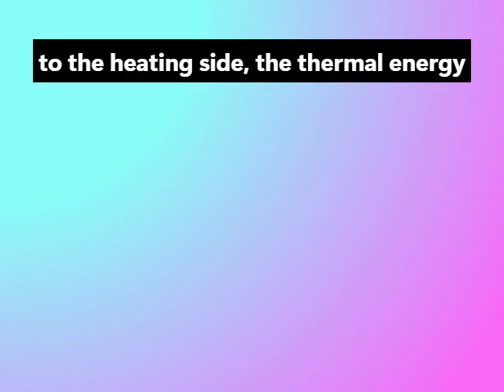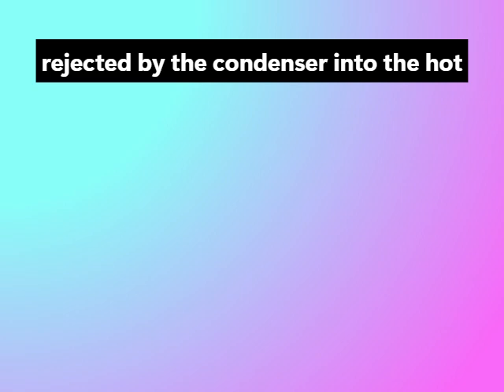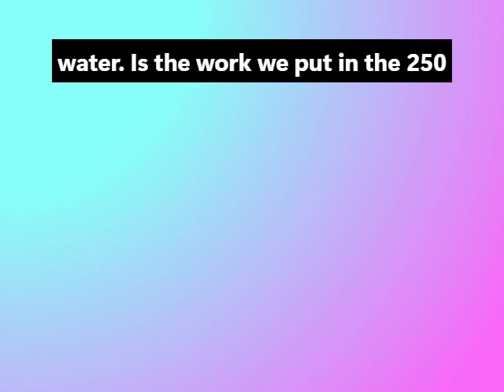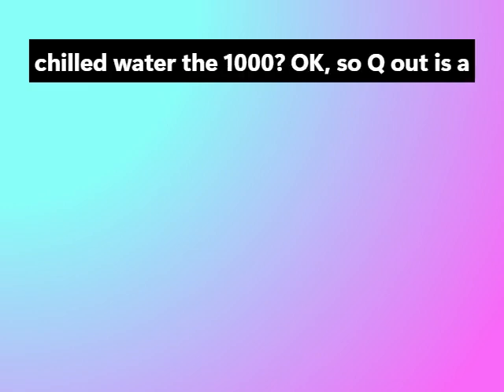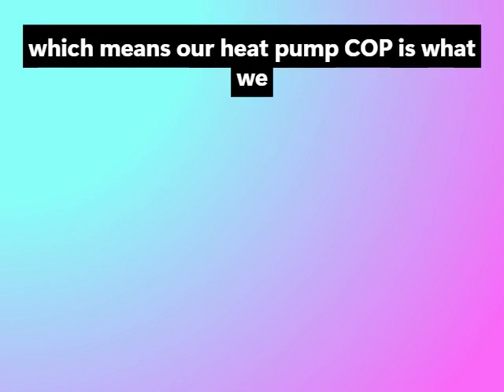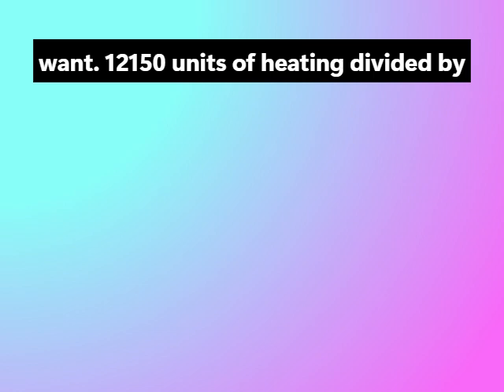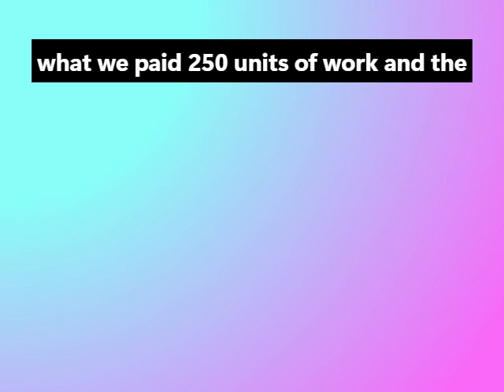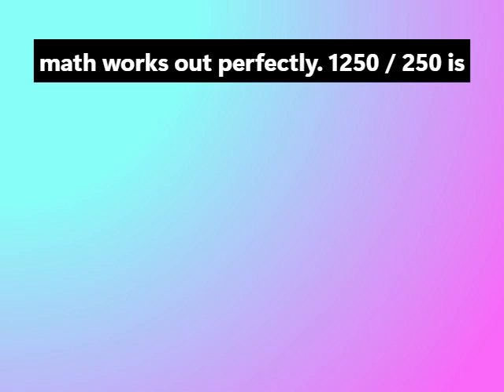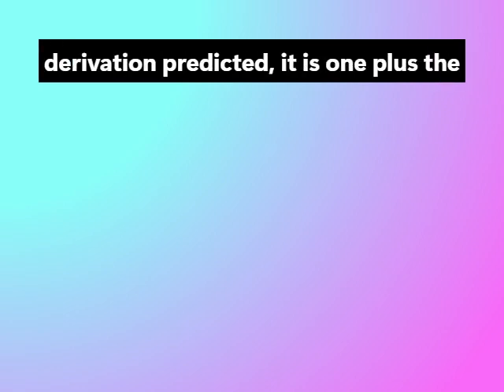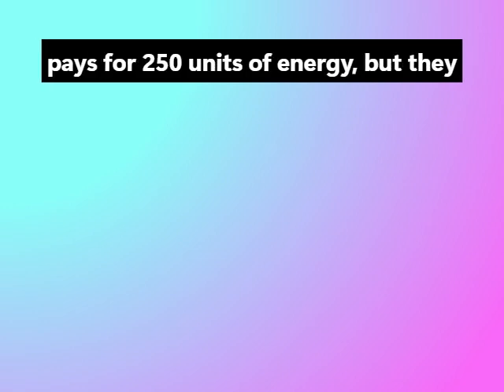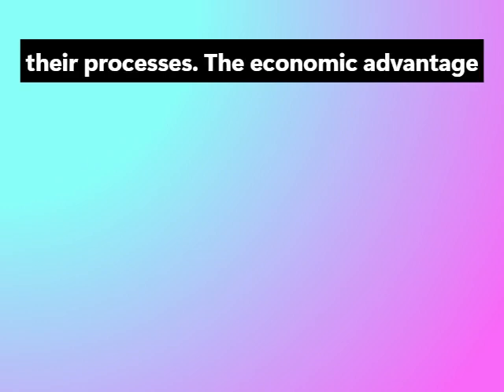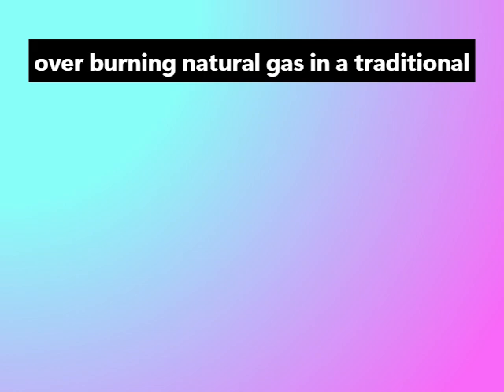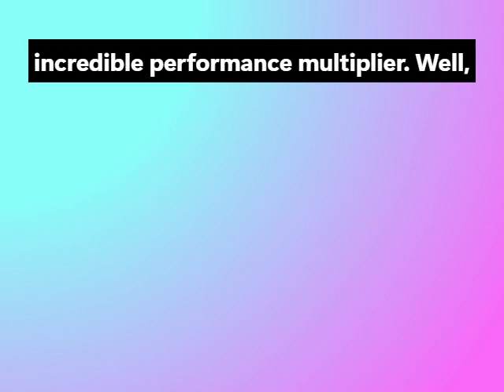Now, trace the energy to the heating side. The thermal energy rejected by the condenser into the hot water is the work we put in, the 250, plus the heat we gathered from the chilled water, the 1,000. So Q out is a total of 1,250 units of thermal energy. Which means our heat pump COP is what we want, 1,250 units of heating, divided by what we paid, 250 units of work. And the math works out perfectly. 1,250 divided by 250 is exactly 5.0. Just as the algebraic derivation predicted, it is 1 plus the refrigeration COP. Exactly. The factory pays for 250 units of energy, but they successfully apply 1,250 units of heat to their processes. The economic advantage over burning natural gas in a traditional boiler is just staggering. It is an incredible performance multiplier.